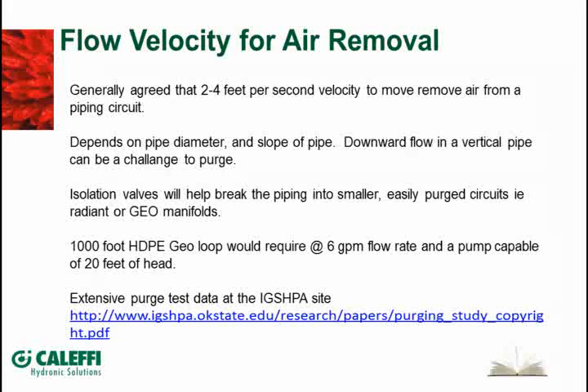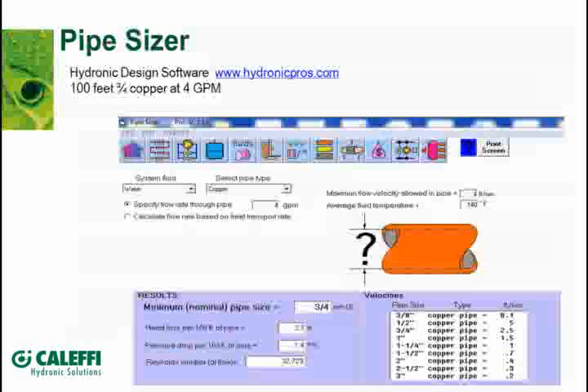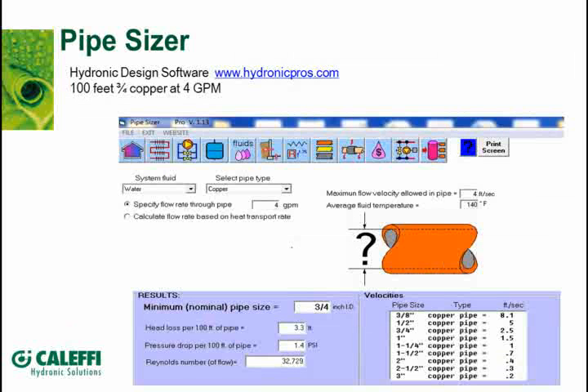Because that's what's going to show up, certainly in a heat pump system, in the summertime when we're under cooling load. You're going to say, gosh, it's not cooling properly. It could be you just got some loops that never got purged out properly on day one, or have some air bubbles in them.